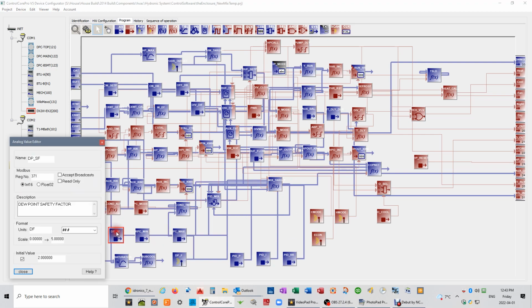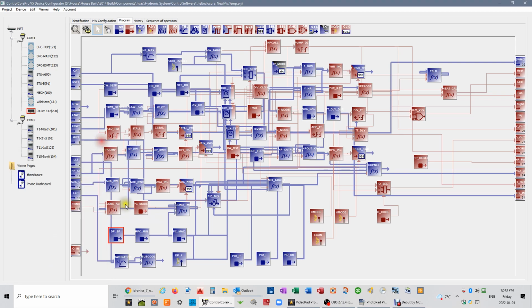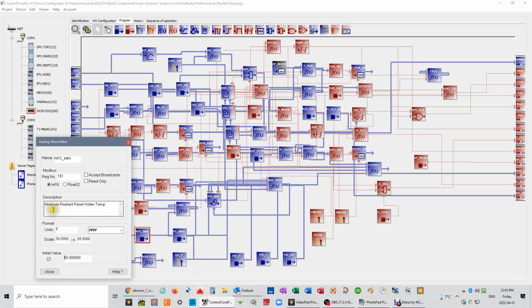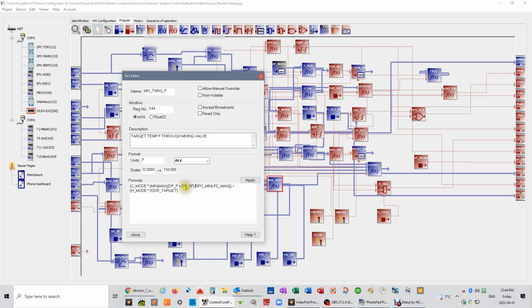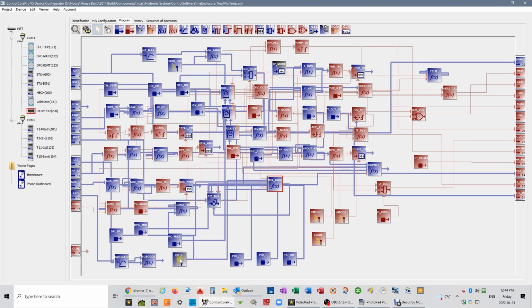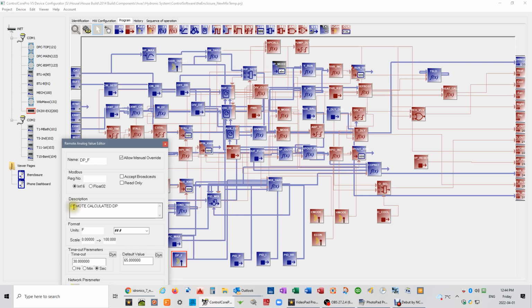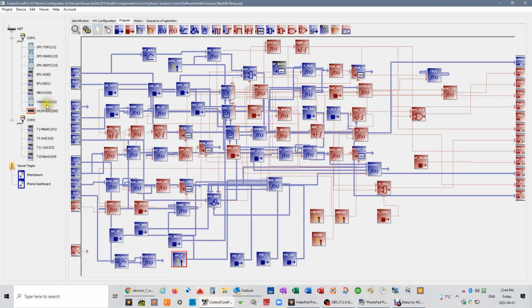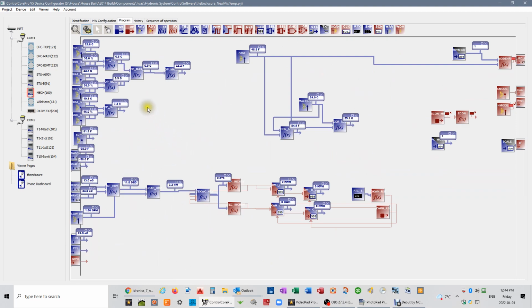So we have dew point SF here, dew point safety factor. Okay, that makes sense. That's the 2 degrees we want to be above dew point. And the RPC minimum is the minimum radiant panel water temperature that we want. So there was the RPC minimum, there was the dew point SF safety factor, and then the dew point F is down here. And that's the remotely calculated dew point, which is what was calculated over here.